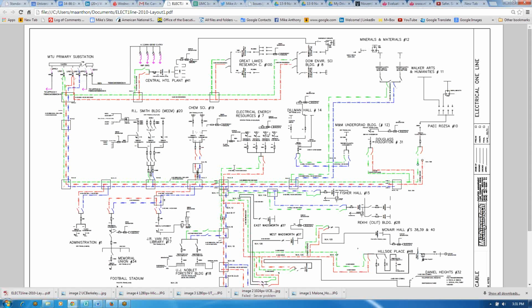We're having the breakers tested because some are quite large, like 4,500 amps — the secondary breakers, the 480 or 208 volt ones. Field buildings run quite high. In some cases we feed other buildings from one emergency generator in another building, sharing the emergency load.